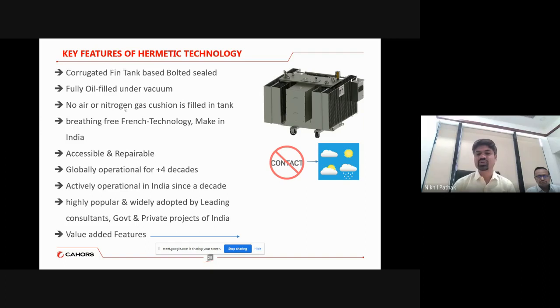As in the case of a conventional transformer, we know that the oil has to be filtered every 1 or 2 years, and repeatedly the oil filtration has to be done. So by using this technology, we avoid the oil contact with the external atmosphere, which gives a healthy atmospheric condition to the insulating oil of the transformer, which remains healthy for a longer time. And that is the reason the periodic operational cost spent on the transformer to keep the oil healthy can be relaxed for 5 years, because we are always suggesting that it is better not to keep a blind approach in the operational service of the transformer.